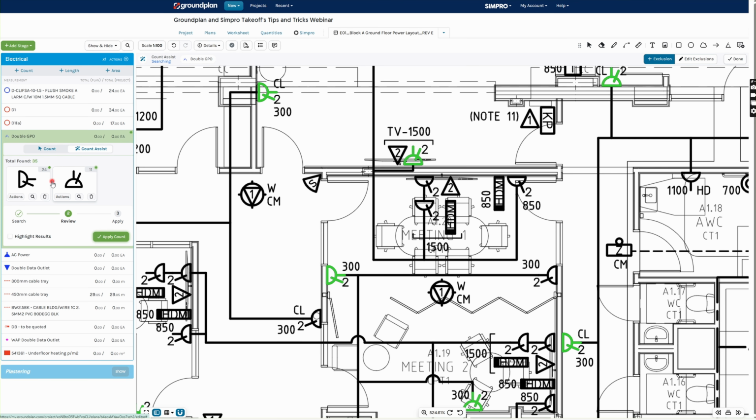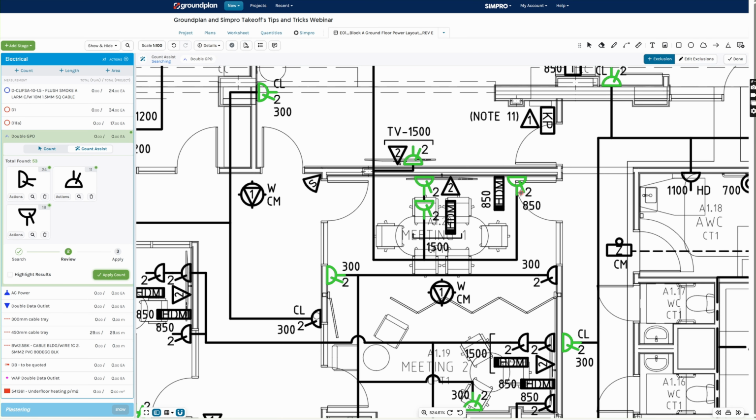So when we're talking about symbols being identical, we're talking about the size. We're talking about the line width. So this D here is a bit skinnier than this D here is, and this line comes in a bit further. So if you were to rotate that to the same way round, those symbols wouldn't line up identically. And it's very common in electrical, especially with PowerPoints, and generally it comes because of revisions that have happened in the background.